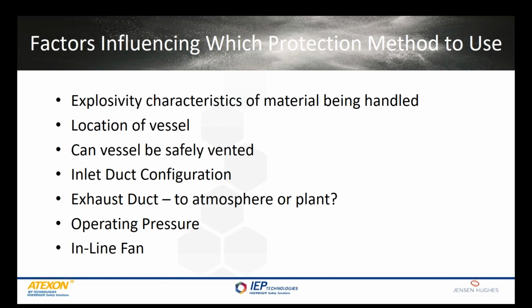For the different explosion protection techniques that we just discussed, there are a number of different things that should be looked at when you're trying to determine which protection methodology would be best for your application. Certainly the explosivity characteristics of the material are very important. As Martin mentioned earlier, most dust that we'll find in a biomass facility is going to have a KST value of 200 or less. So it's an ST1 dust. One sidebar on that, between 85 and 90% of all combustible dust falls into that ST1 category.